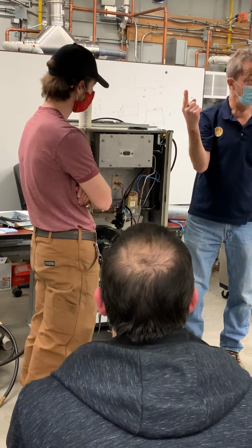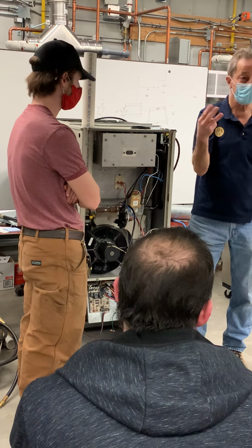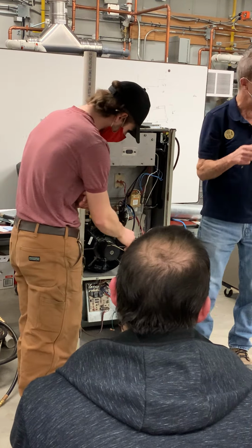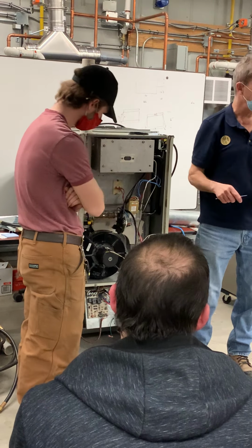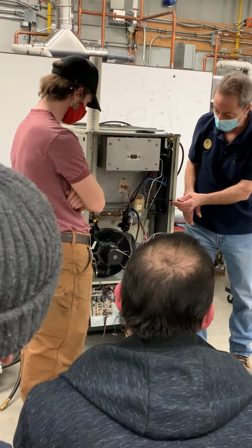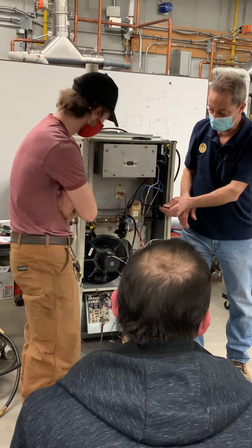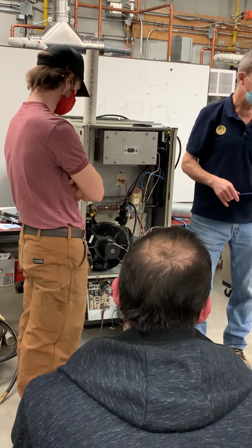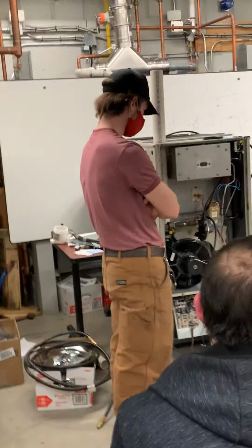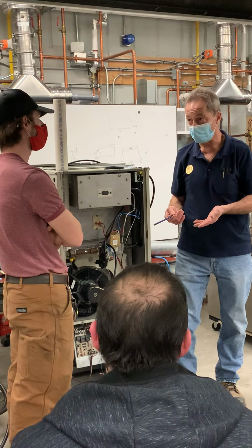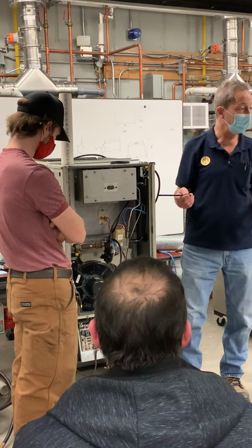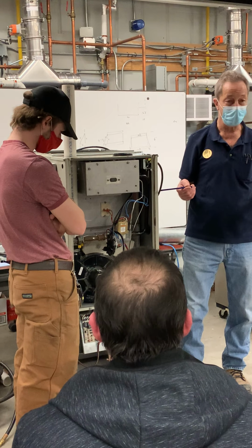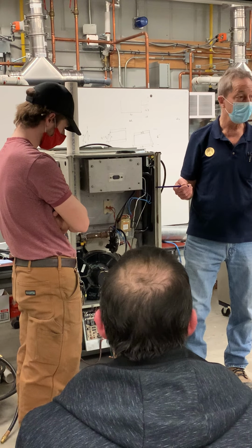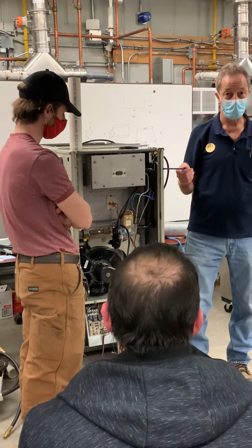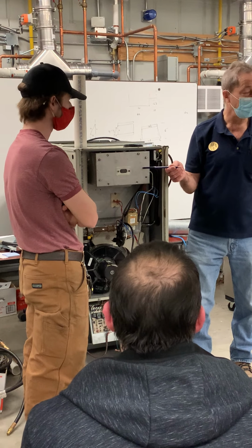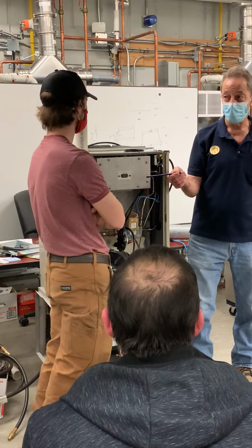Right, correct? Yes. So based on that, 3 wires going in, this is part of the process where I say, look at something, know what it is. As soon as you see a Honeywell valve, 2 plugs on the top, you know it's a smart valve. You know it's 24 volts. You know it's a 24 volt HSI. You know the 2 blue wires are generally going in for the HSI. You know you got a single black wire going in, flame sensor. You know you got a sealed burner compartment. You got a pilot burner in here.